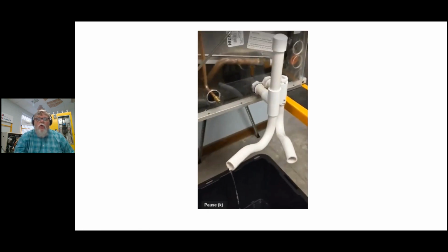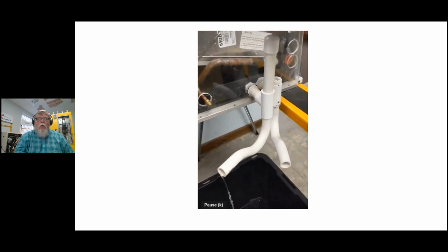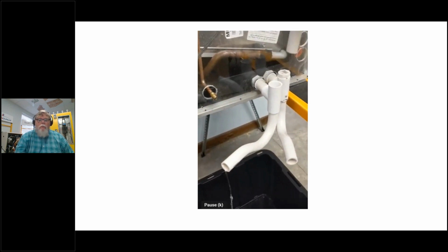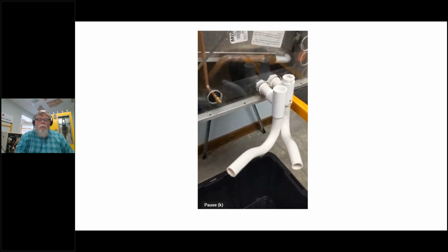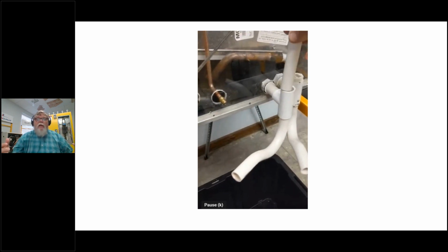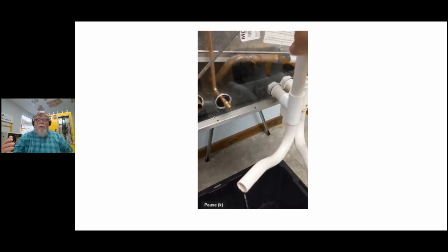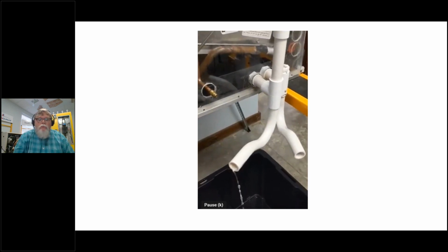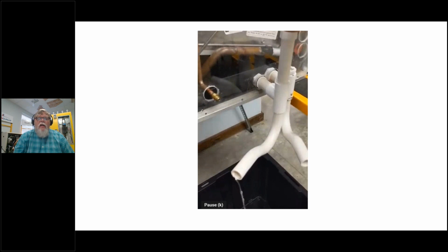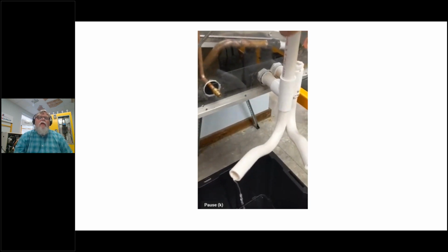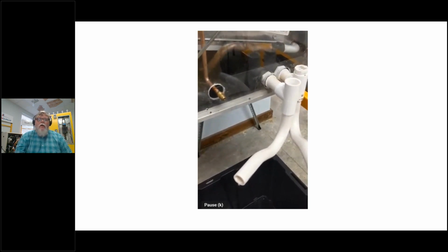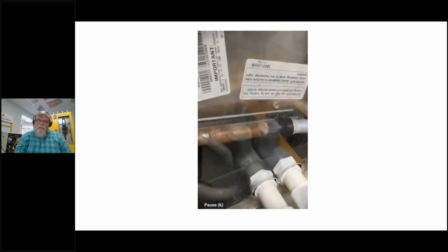All right, notice the water's dripping out of that one there. Now watch when I pull the plug, when I pull the cap. It stops. Now the unit's making condensate, it's filling up the pan. I put it back in and plug it off, it starts draining again. And that's where they fail. People will leave that line open there. If you want to have a T and an open line on the other side of the trap, that's fine, but not that side. It makes the trap useless. Look at the water being sucked back in there.